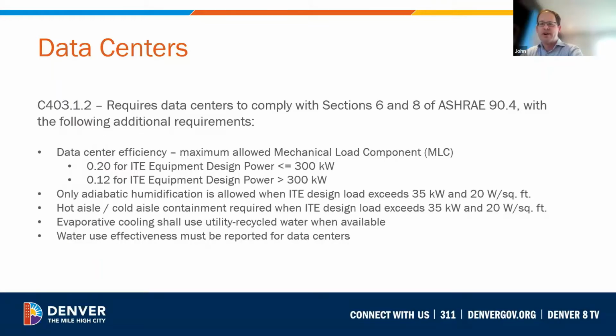Also, pertaining to the water side, the code requires the use of recycled water where available. If there's no recycled water available and there's only potable water available, then that would be an exception to this requirement. Some large data center providers use water treatment as a way to treat gray water so that it can be used in evaporative cooling towers. Without going into detail, evaporative cooling towers, while efficient from an energy perspective, consume a great deal of water. So there's a trade-off, and there's an increasing desire to limit the use of potable water for data centers.